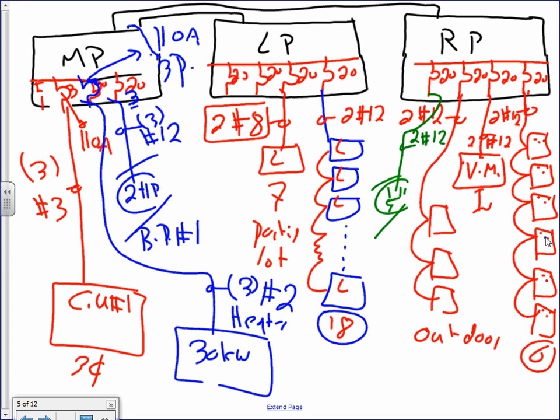I have a 30 kVA heater, guys. I fit this one from, what's the circuit for that boy? Now remember, these are 3-pole. I have 3 conductors number 2 for the 30 kVA heater. I can't remember what the overcurrent device is here. Is it 30 amps? I think we're going to do that one in a second. We're going to come into this.